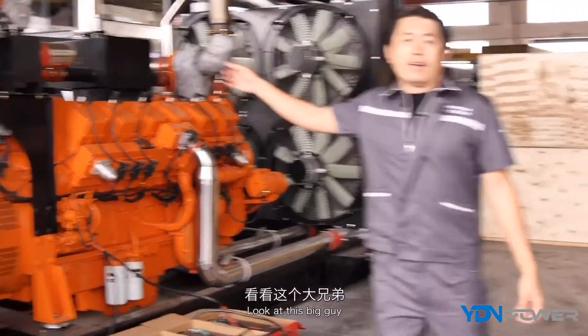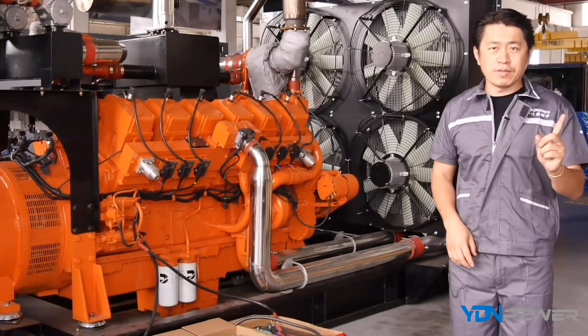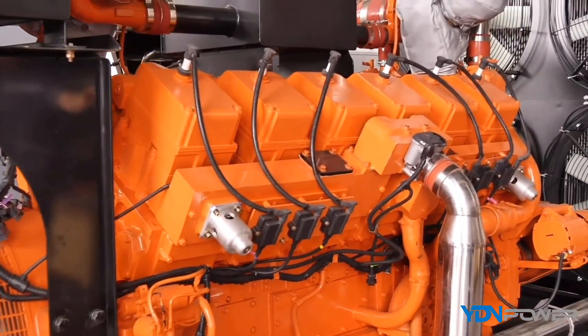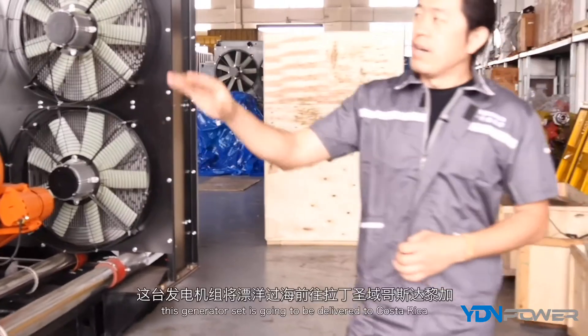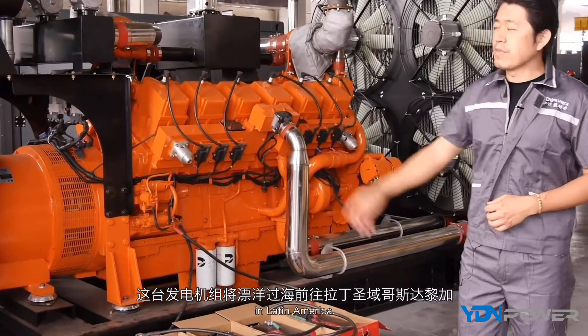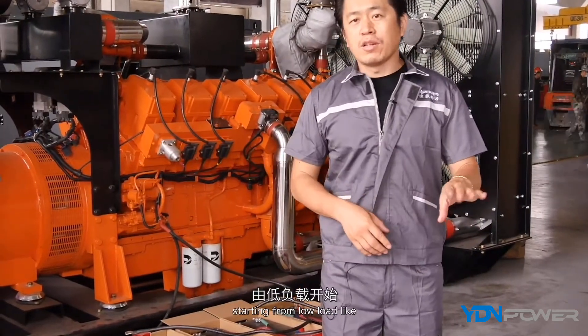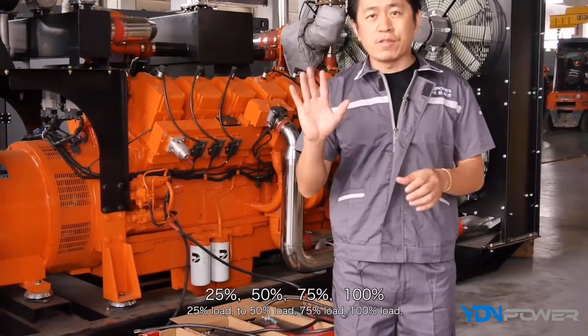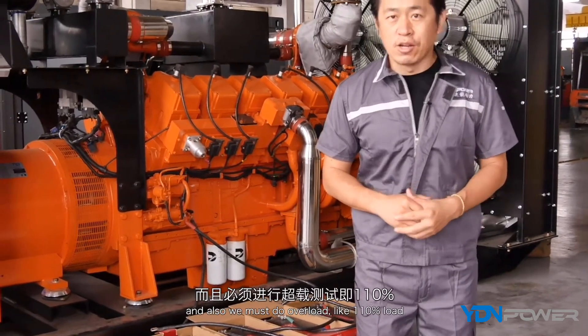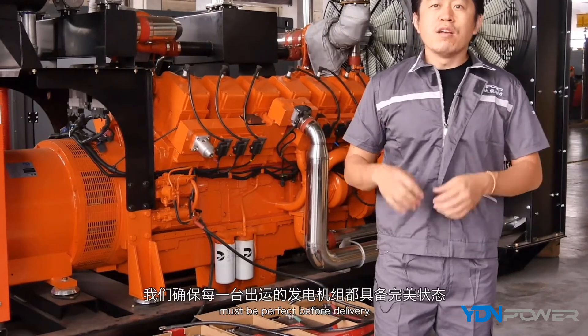Look at this big unit. This area can test up to 1,000 kilowatts — that's one megawatt. This one is powered by the Cummins KTA38 engine at 500 kilowatts. This generating set is going to be delivered to Costa Rica in Latin America. When we do testing, we follow ISO standards exactly — starting from 25% load, then 50%, 75%, 100%, and we also do overload testing at 110%. This is how we confirm and guarantee perfect quality before delivery.